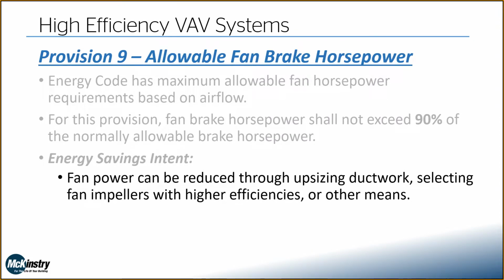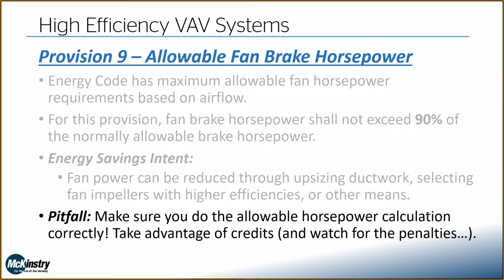The intent here is to reduce our fan power through upsizing our ductwork, selecting more efficient fan impellers, or making sure we're using fittings that have less pressure drop than our standard fittings. Anything you can do to reduce static pressure and reduce your fan horsepower. But make sure you're doing that calculation correctly. We've seen many times that the allowable horsepower calculation is not done right.